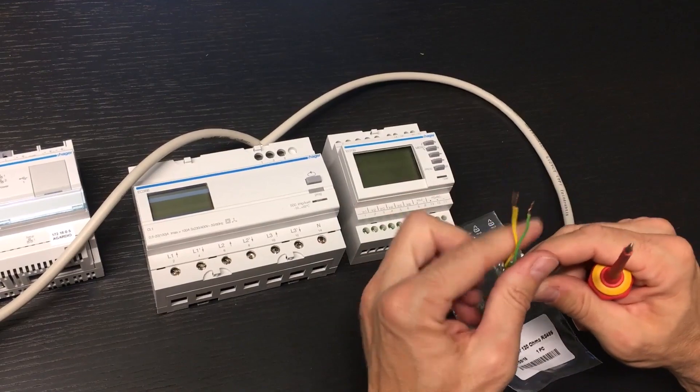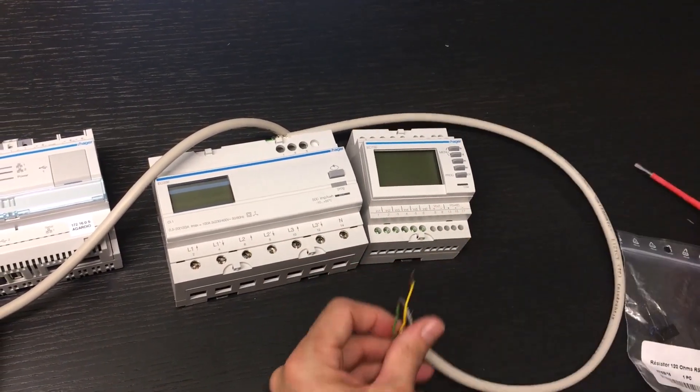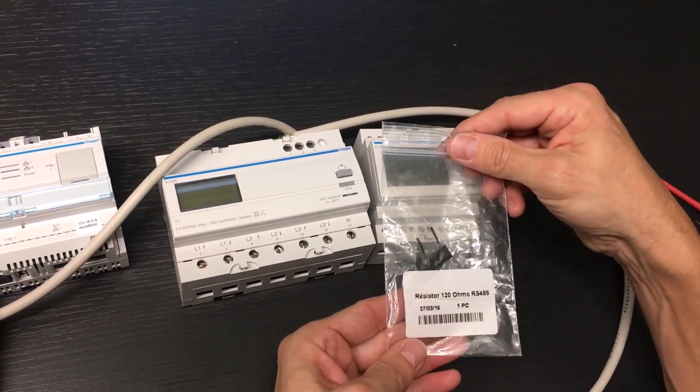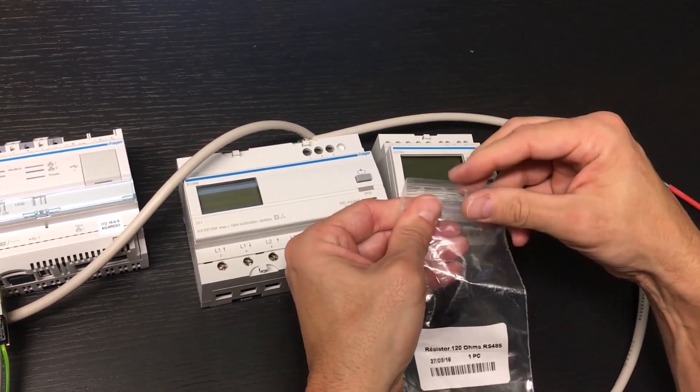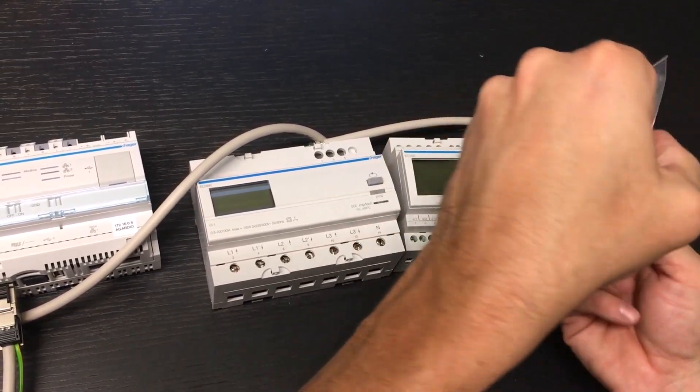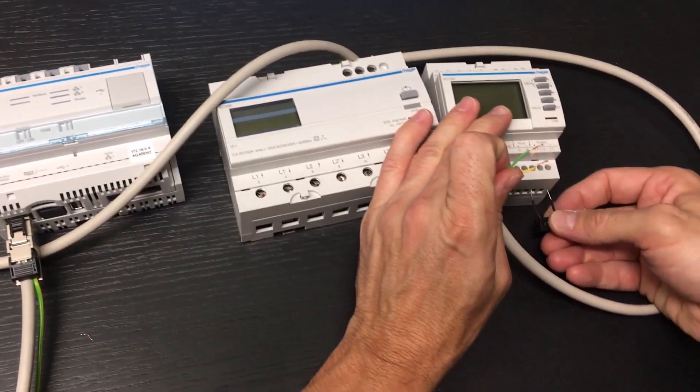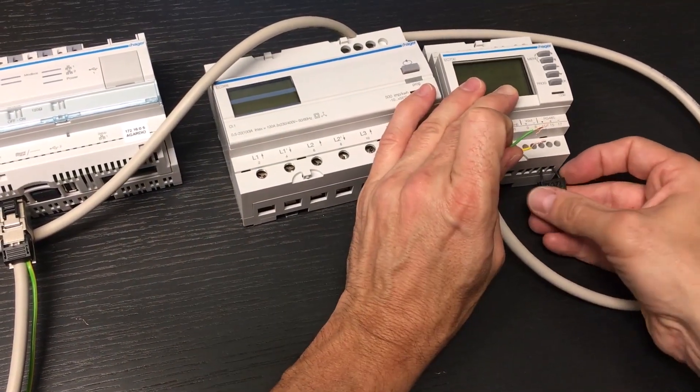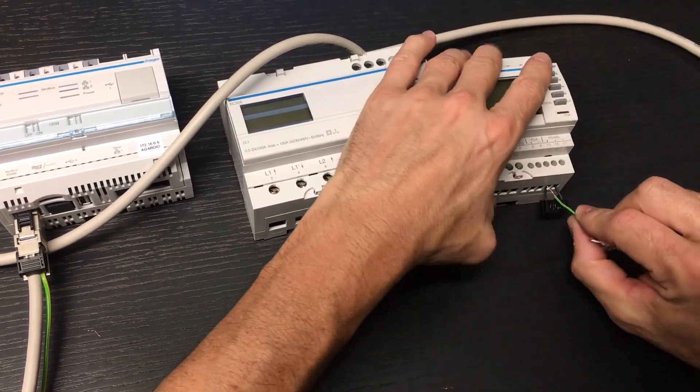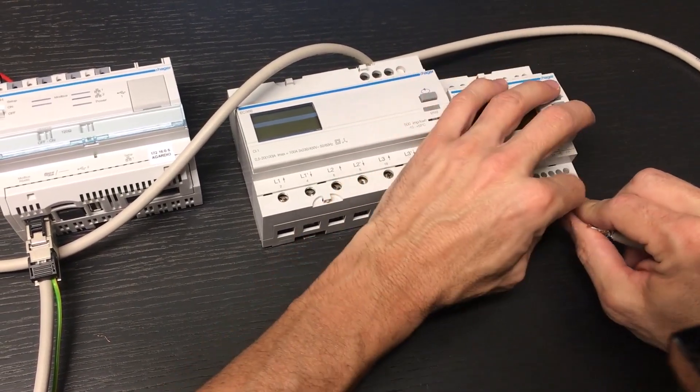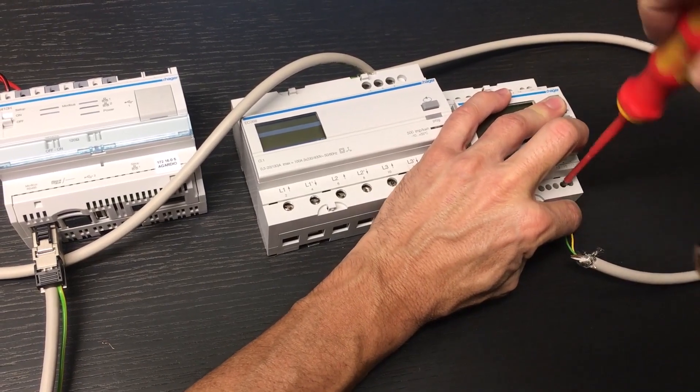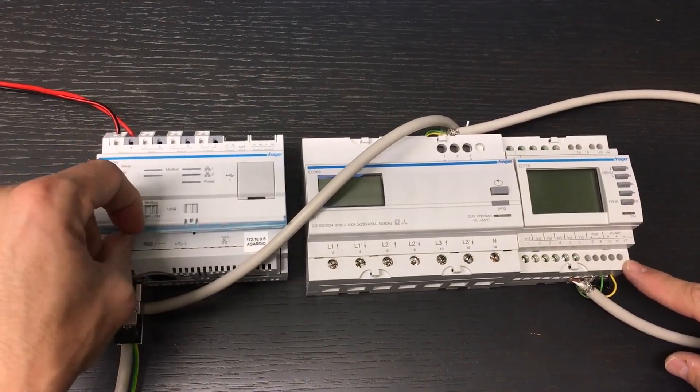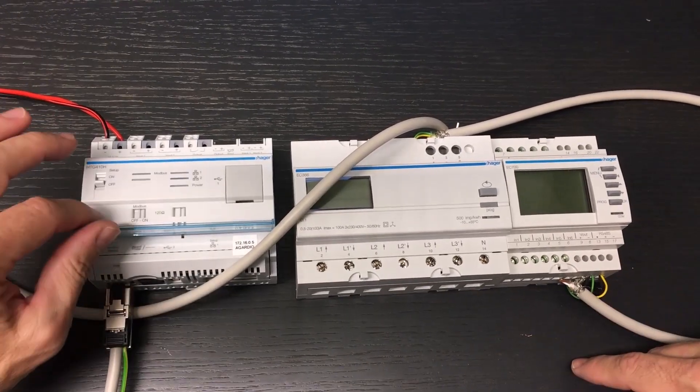Now we take the end of the last cable to connect it to the Modbus terminals. A 120 ohms termination resistor must be added to the product ends. It is already integrated on the first product using the switch on the front panel.